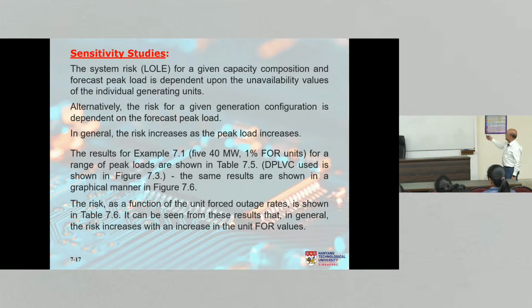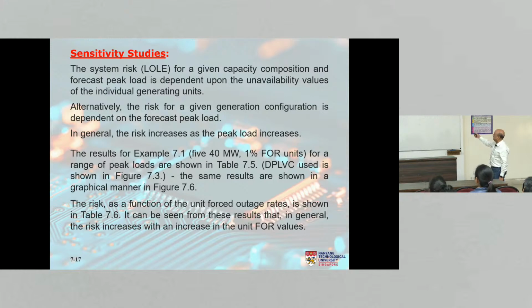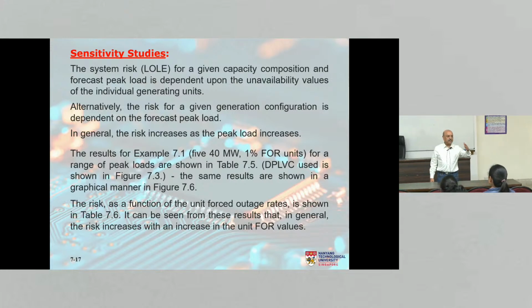So the system risk for a given capacity composition is dependent upon the unavailability values of the generators. How? We'll see shortly. Alternatively, I can also argue that the risk is dependent on the peak load, isn't it? Just now in the example, we saw that the peak load was 160 and the installed capacity was 200, right? So if I change the peak load, do you think that the risk will remain the same? Generally, you would expect that if the peak load increases, the risk will also increase. And if the peak load reduces, the risk will also reduce. So you have a way to quantify those things through these techniques. Intuitively, we know which way it's going to go, but how much, we don't know, right? We can only use these algorithms.